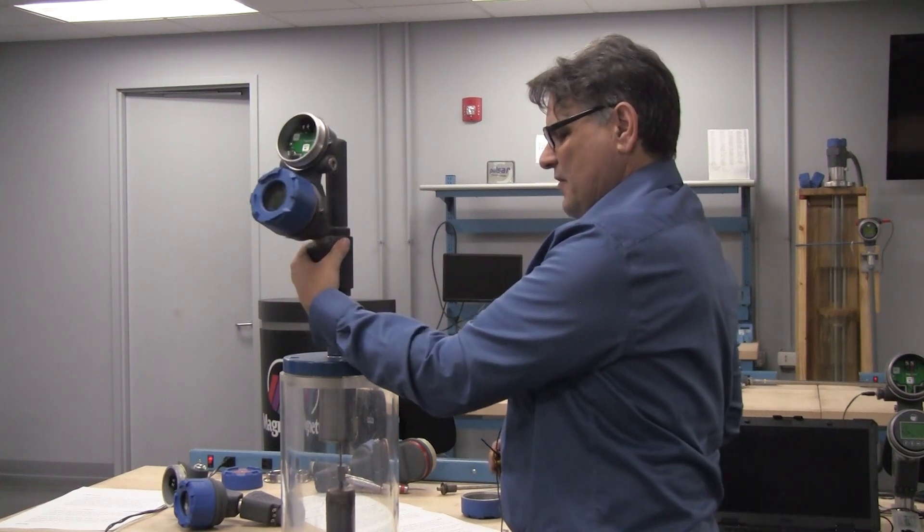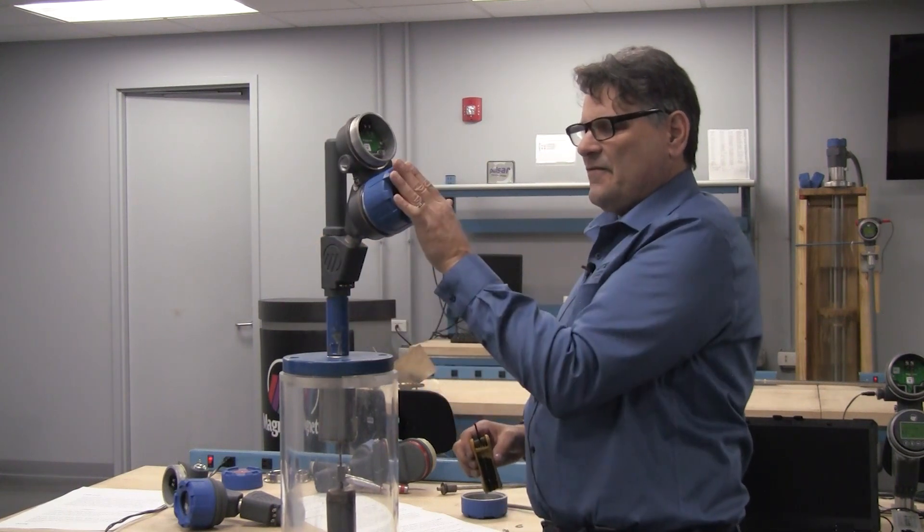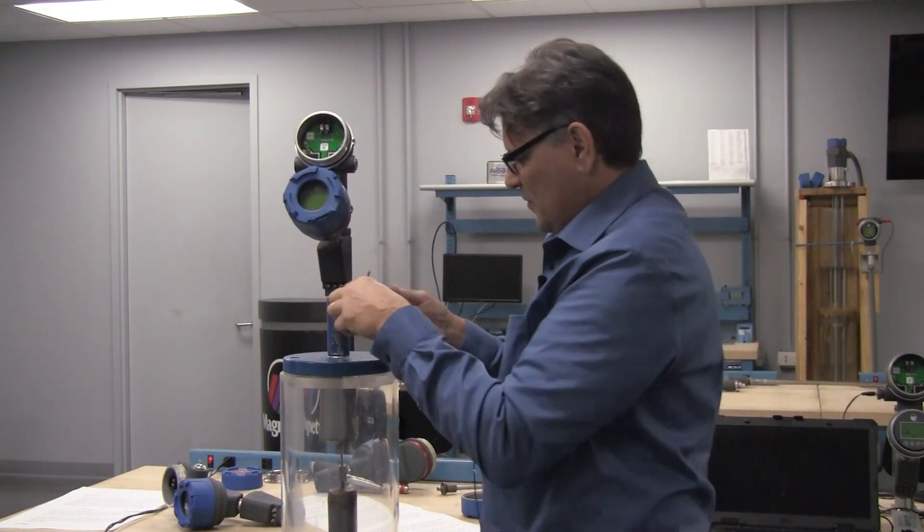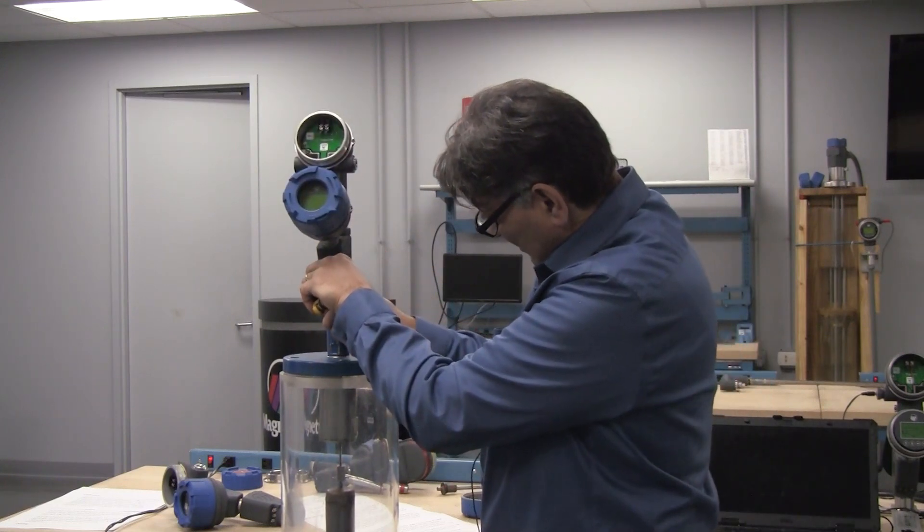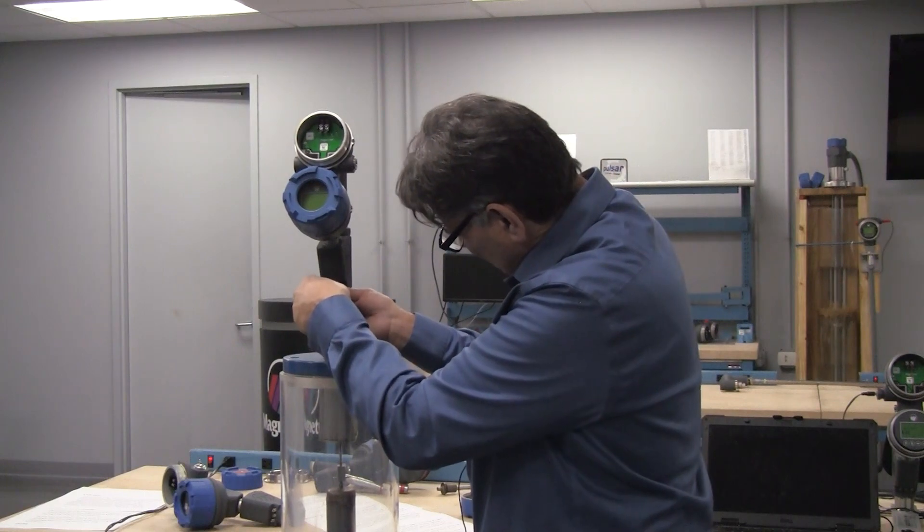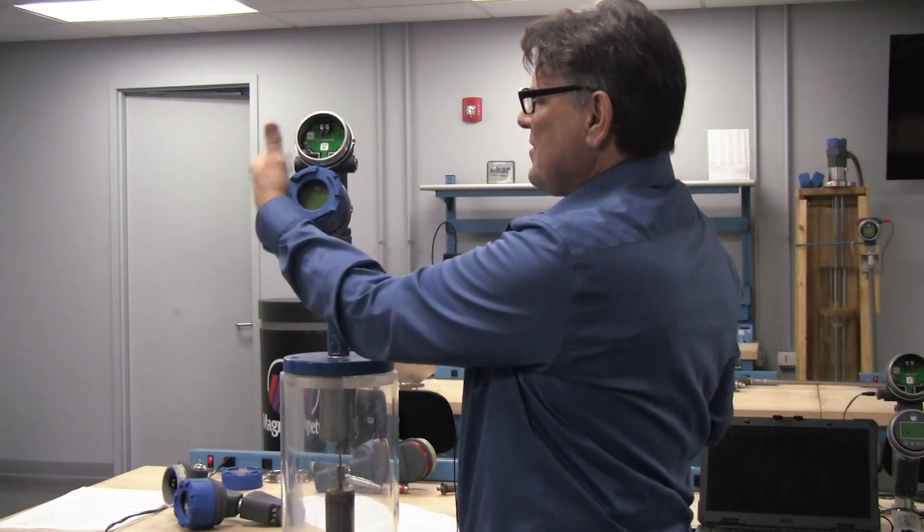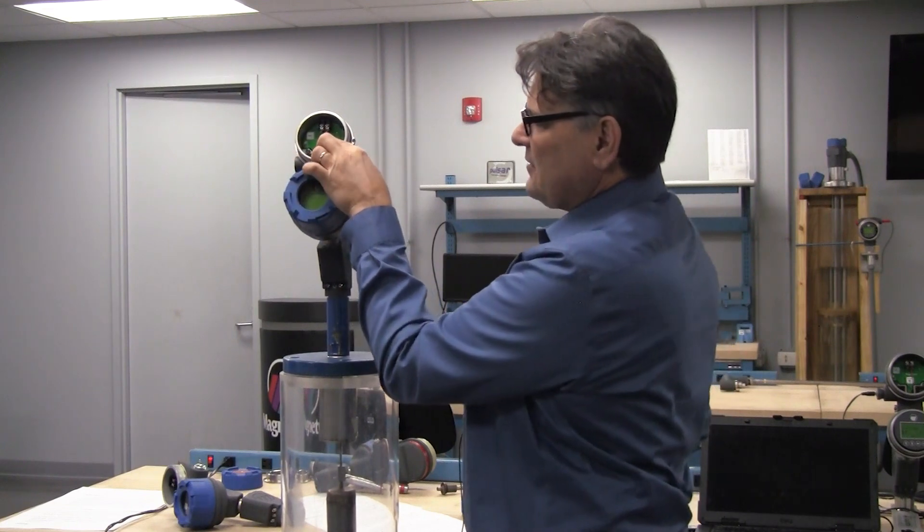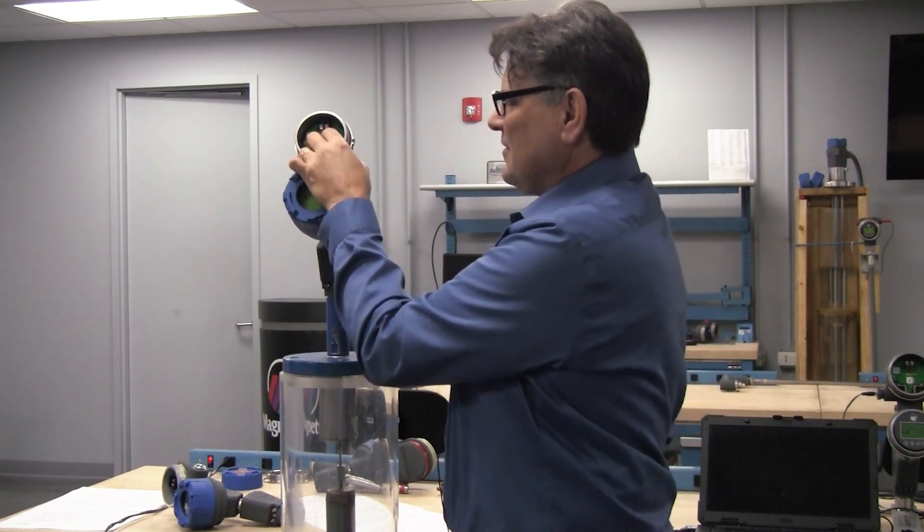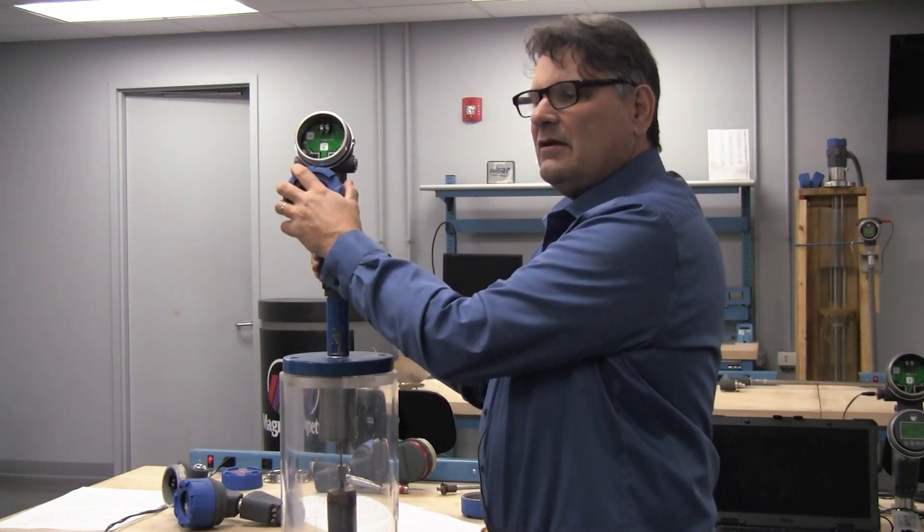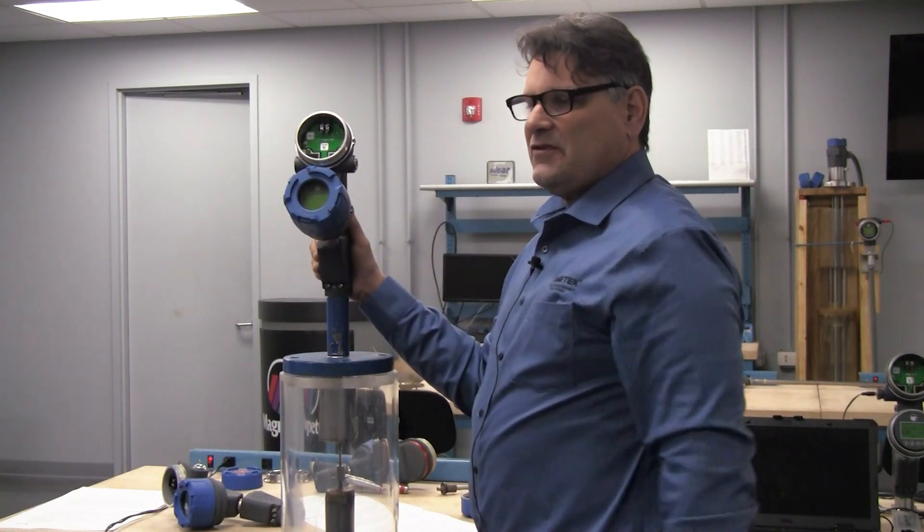Now you can rotate the transmitter to provide whatever orientation for the display you would like, so in my case I'll just point it out straight. I'm going to tighten up the eighth inch Allen screws. Now you would run your wires in, attach your loop, positive to positive, negative to negative up here, and you are now ready to perform the calibration of the unit.